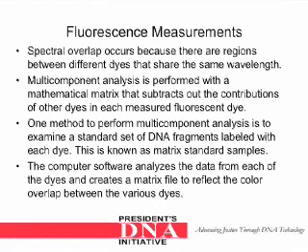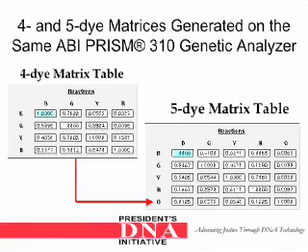Fluorescence measurements: spectral overlap occurs because there are regions between different dyes that share the same wavelength. Multi-component analysis is performed with a mathematical matrix that subtracts out the contributions of other dyes in each measured fluorescent dye. One method is to examine a standard set of DNA fragments labeled with each dye, known as matrix standard samples. The computer software analyzes the data from each of the dyes and creates a matrix file to reflect the color overlap between the various dyes. Here is an example of what a four-dye matrix table and a five-dye matrix table will look like.